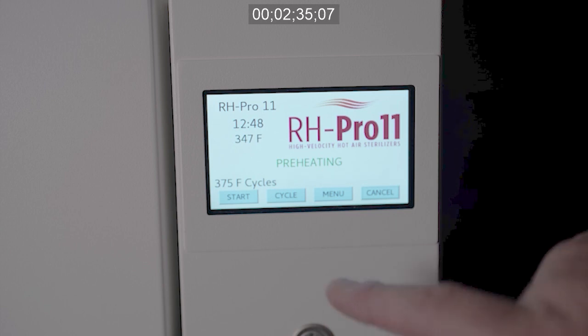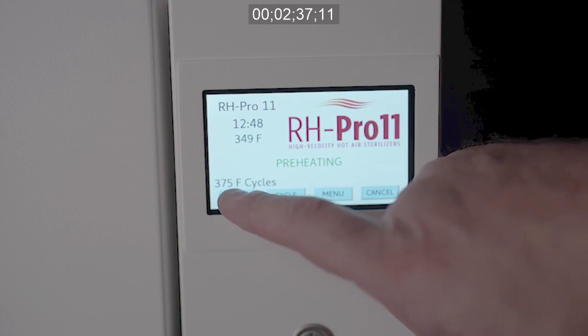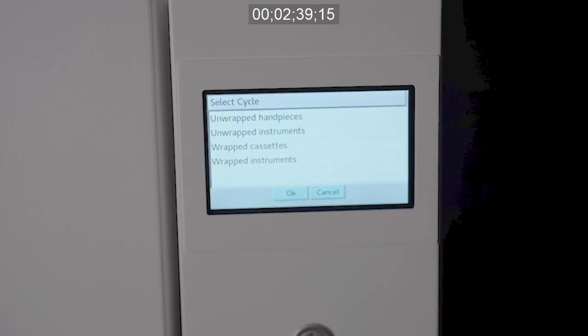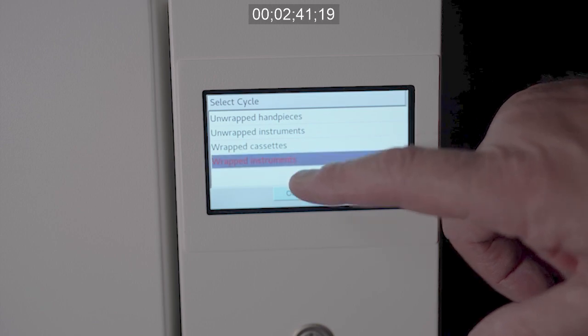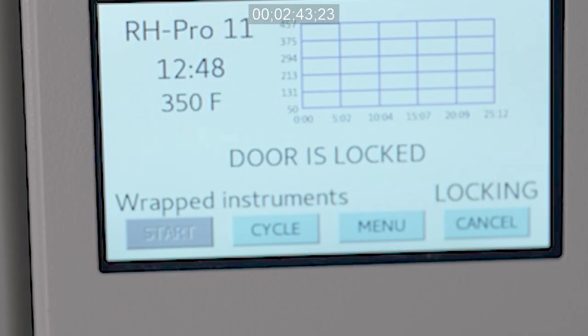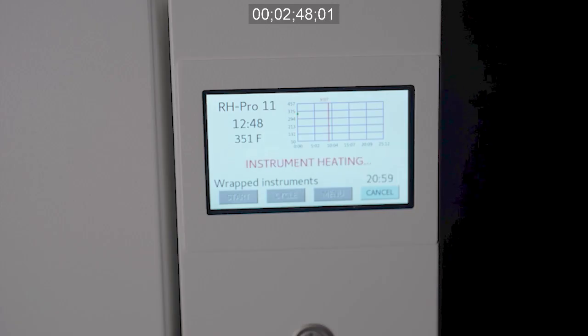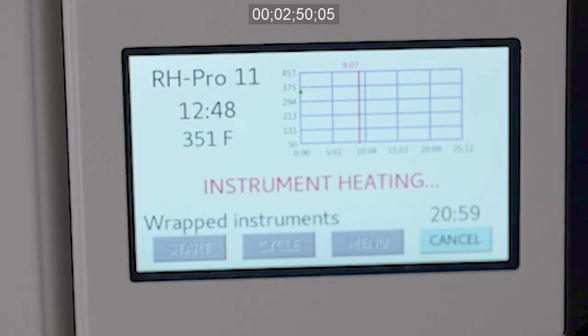To initiate a sterilization cycle at the 375 temperature from the Ready screen, first press Start, and then choose from the Select Cycle display screen the cycle that identifies the type of load that you are sterilizing. During the sterilization sequence, the Door is Locked screen will appear, followed by the Cycle in Progress screen that shows a graph that tracks the temperature during load warm-up and sterilization.